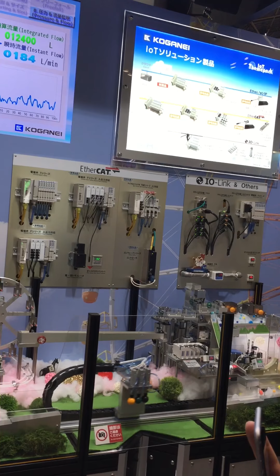The advantage, of course, is that as soon as you have an IO-Link compatible product and you hook it into an IO-Link master, it understands what it is. For example, there's a pressure sensor mounted there. If that pressure sensor is hooked into the IO-Link master, and there are any parameters set up through IO-Link into the pressure transducer, and a maintenance person has to change the transducer out, when they put a new one on, the IO-Link module will automatically download the parameters into it. The mechanic or maintenance guy doesn't have to do any setup. It does it automatically. In 100 milliseconds, it downloads the information and it runs.